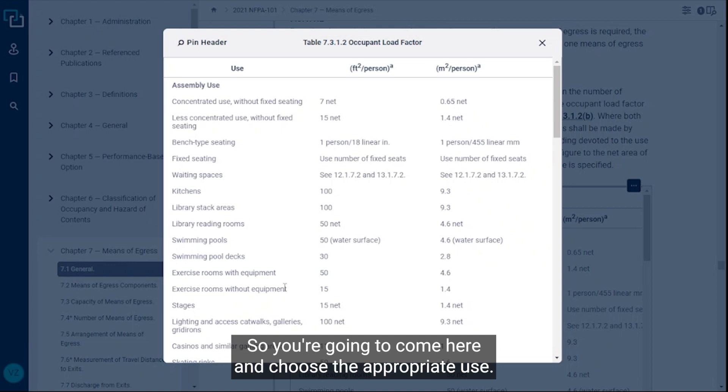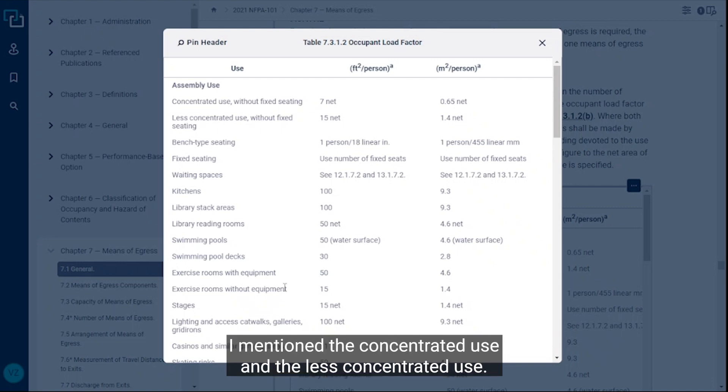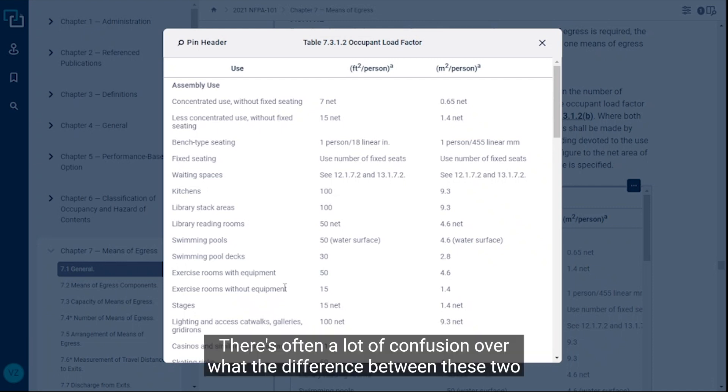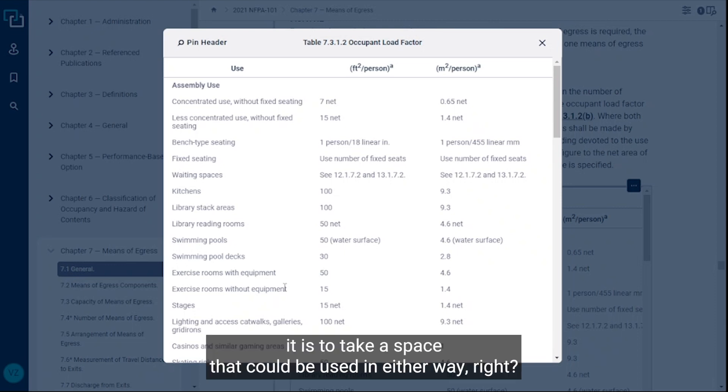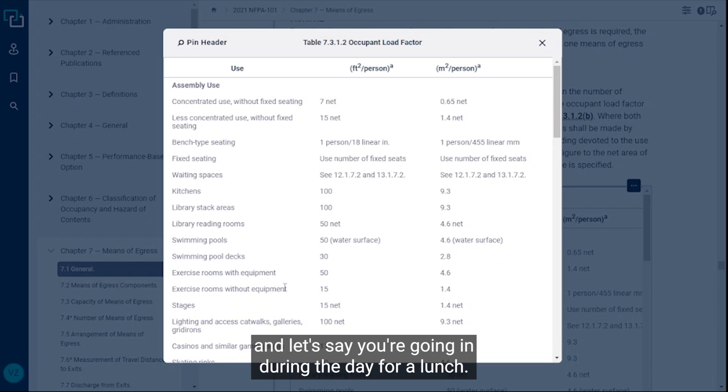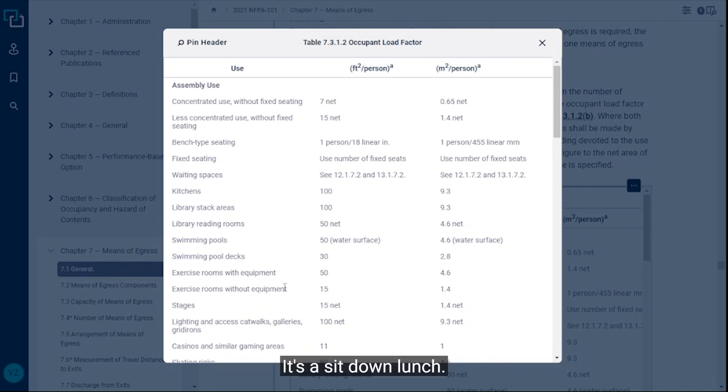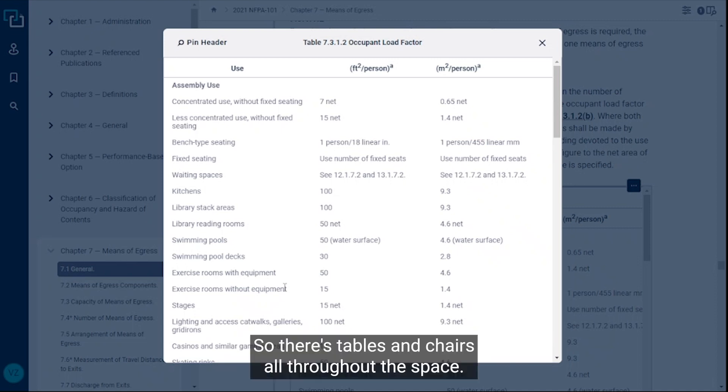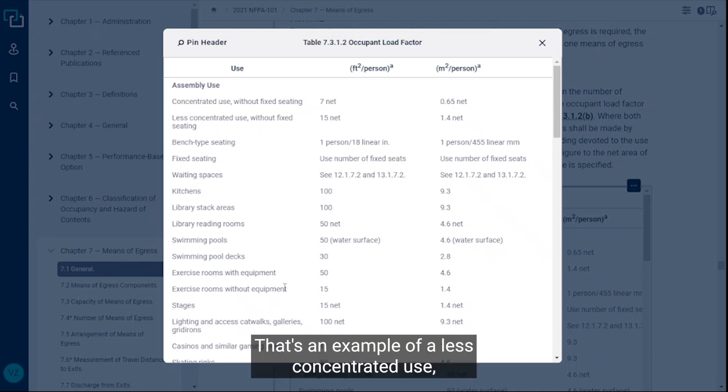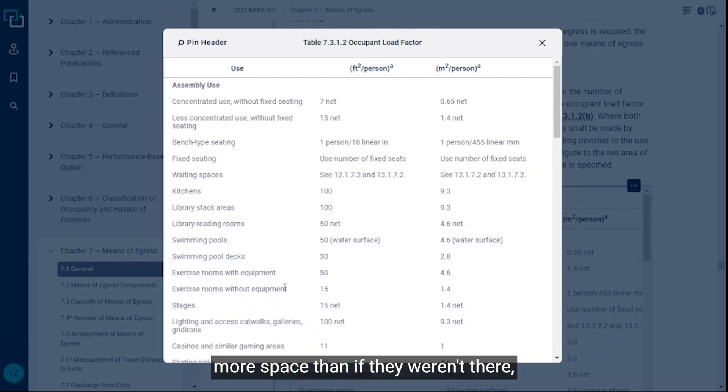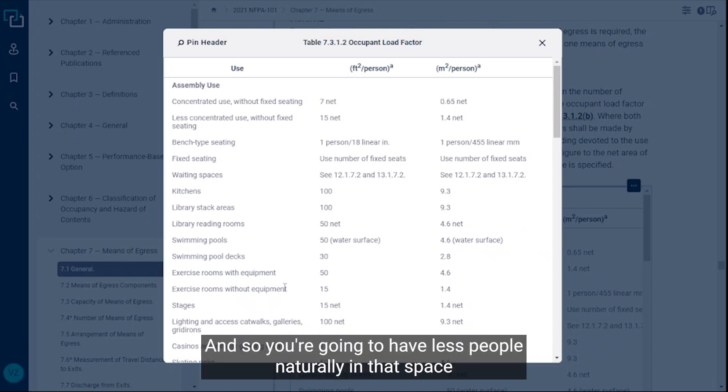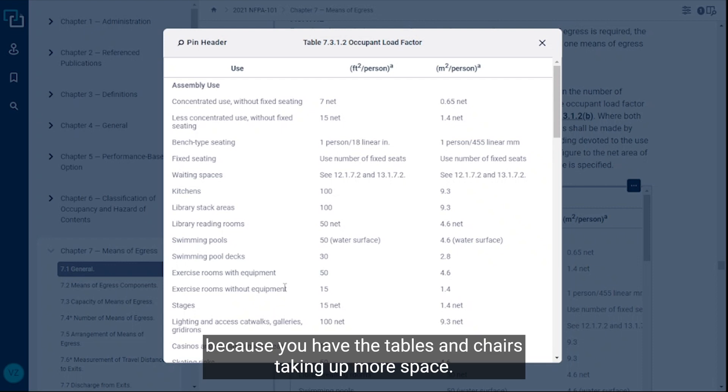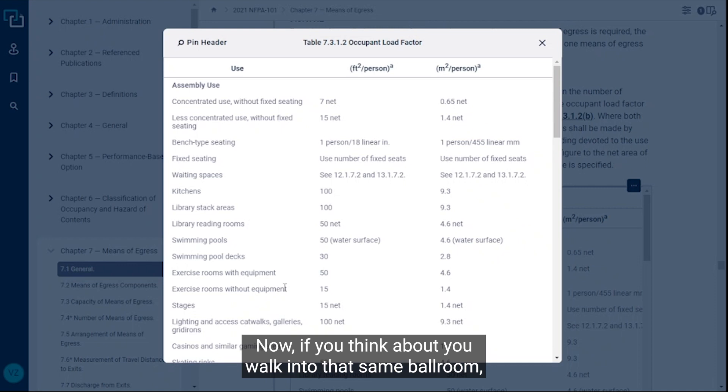One other thing I want to talk about is those two assembly uses I mentioned: the concentrated use and the less concentrated use. There's often a lot of confusion over what the difference between these two is, and the way I like to think about it and explain it is to take a space that could be used in either way. Let's say you're in a hotel and they have a big ballroom area. Let's say you're going in during the day for a lunch, and so they have tables and chairs. It's a sit-down lunch, so there's tables and chairs all throughout the space. That's an example of a less concentrated use, because if you think about it, the tables and chairs are taking up more space than if they weren't there. You're going to have less people naturally in that space because you have the tables and chairs taking up more space.